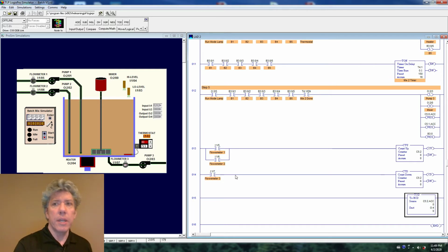Now, there's an interesting effect that happens if I do this where I'm counting here. For some reason in this simulator, you can end up putting in 300 units, but it's actually 301, and then when only 300 come out, you still have a volume of one count in the tank, at least according to this counter. And so slowly but surely this display creeps upward. It'll go to 301, 302, all the way to, I let it go and it went all the way to 309 after about an hour or so. Now that's not good. If I've emptied out the tank, there should be nothing in it.